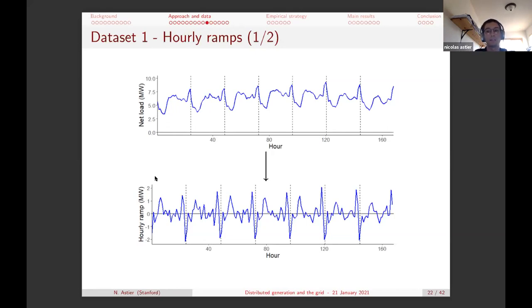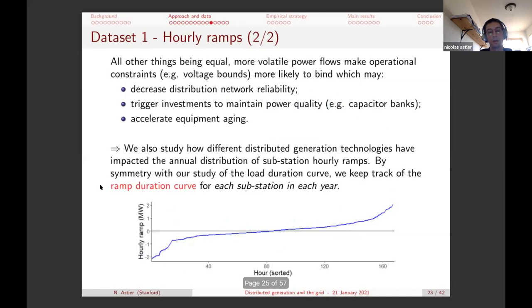What we are looking at is the same concept, but at the distribution grid level. We take the hourly net load level of a substation and take first differences: one hour minus the previous one. For example, here load is increasing, so you have a high ramp upward. After that, load is decreasing, so you have a low ramp. By analogy with the load duration curve, we also keep track, for each substation in each year, of this ramp duration curve, which gives you the distribution of ramps you have seen for this substation by increasing magnitude.